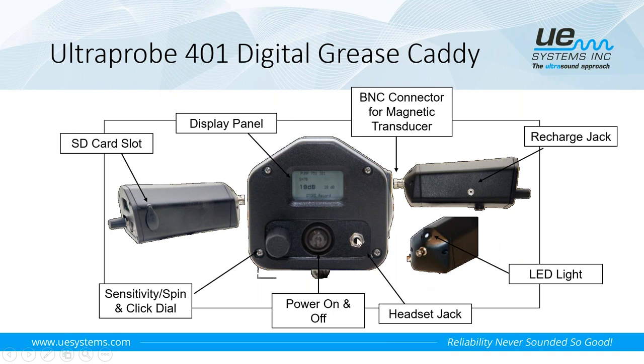You'd always want to make sure you wear the headset. Even though we can get a visual here on the display, it's still a good practice to listen to that bearing and not rely solely on what you're seeing visually on the instrument. Of course, your power on and power off, and then the sensitivity spin and click dial. So this dial serves a dual purpose. Not only can we scroll left or right to adjust things, adjust sensitivity, but we can also press and release that sensitivity dial, and that's how we're able to navigate around the screen to our different features and adjustments.